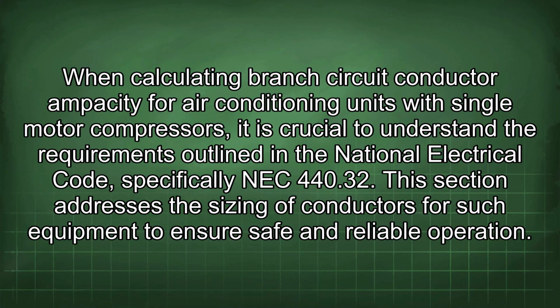When calculating branch circuit conductor ampacity for air conditioning units with single motor compressors, it is crucial to understand the requirements outlined in the National Electrical Code, specifically NEC 440.32. This section addresses the sizing of conductors for such equipment to ensure safe and reliable operation.